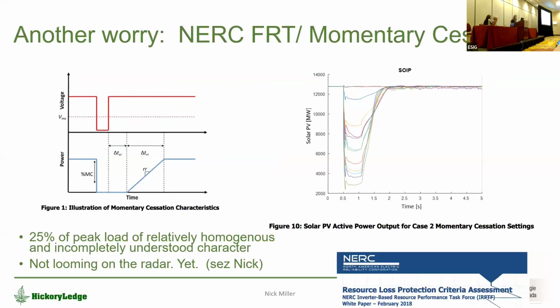Another quick note is that we have to worry about what happens when you've got a whole bunch of your load that's of a relatively homogeneous character. Is there some common mode operational performance thing that could happen when you've got a lot of aggregated one type of load? Like a ride-through issue that could happen if a lot of stuff trips offline in a common mode manner during a fault event, causing frequency issues. So there are other things we should think about.